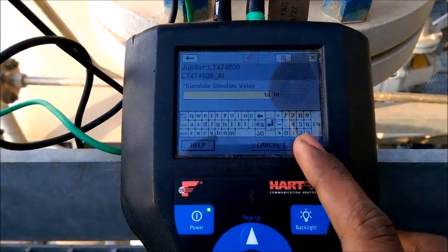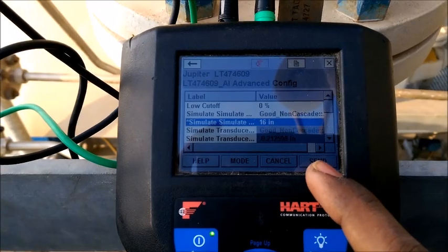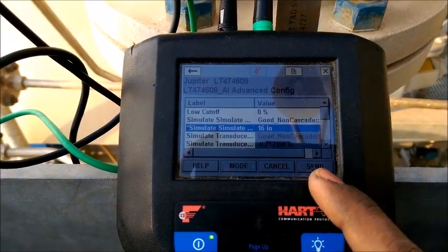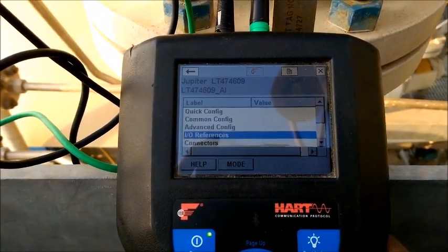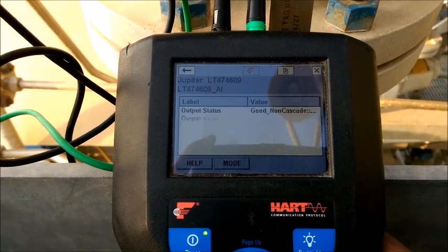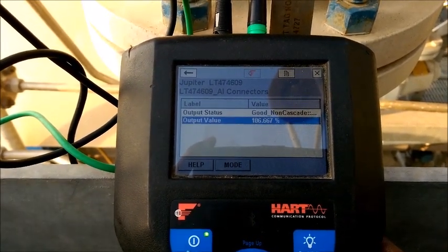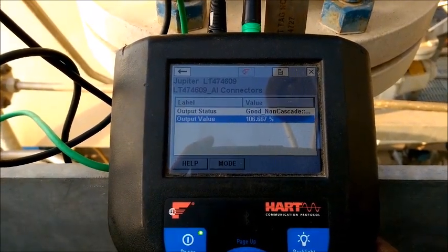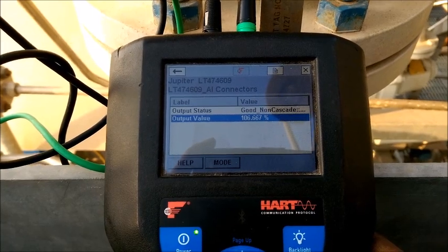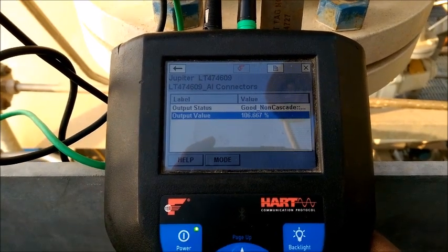Now I want to make the over range. Here I make it 16 inches — you can see it is showing over range. You can see the value showing as 106.667 percent. This is the over range.